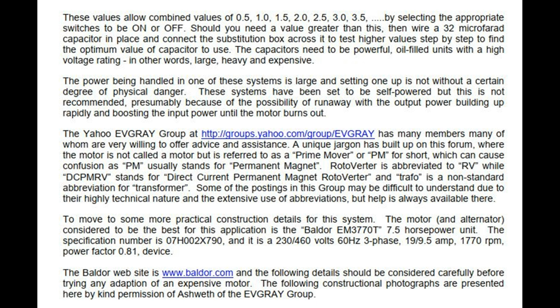To move to some more practical construction details for this system. The motor, and alternator, considered to be the best for this application is the Baldor EM3770T 7.5 horsepower unit. The specification number is 07H002X790, and it is a 230/460 volt 60 Hz 3-phase, 19/9.5 amp, 1770 RPM, power factor 0.81, device. The Baldor website is www.baldor.com, and the following details should be considered carefully before trying any adaptation of an expensive motor.